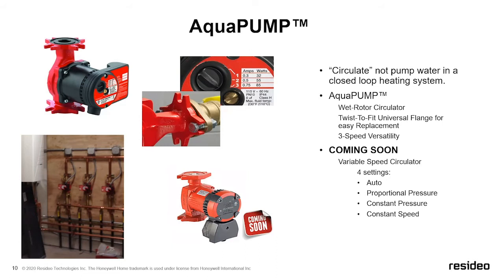It needs to be in the orientation that you see there in the image. If you don't have it in that spot, you're going to have premature failure on the pump. So that 90-degree, or call it 4-bolt flange, gives you the flexibility to put that pump in just about any replacement opportunity that you run into. So if you've got a competitor's product that you're pulling out and going to slap this in, some flanges are rotated 90, some are 0 degrees, so you don't have to worry about unsweating the flanges from the piping. You can leave everything in line and just put it right in.